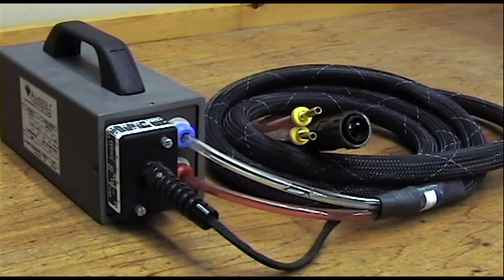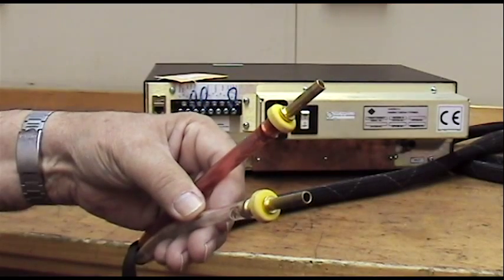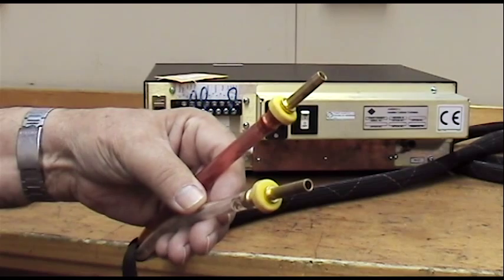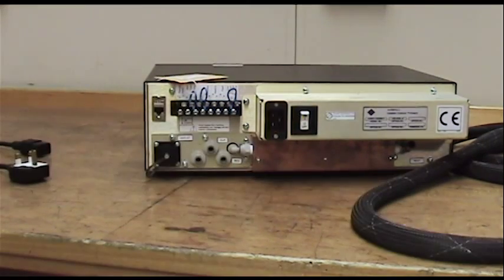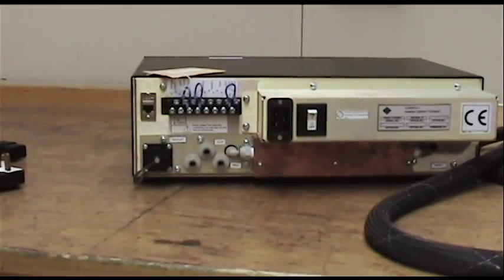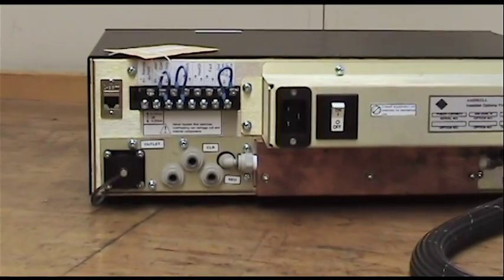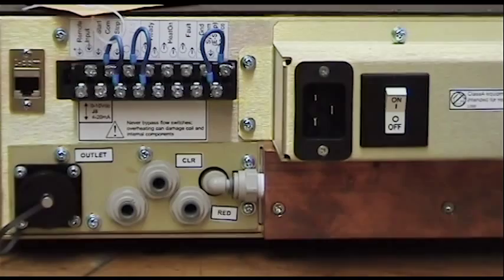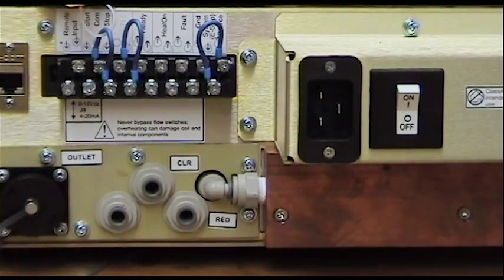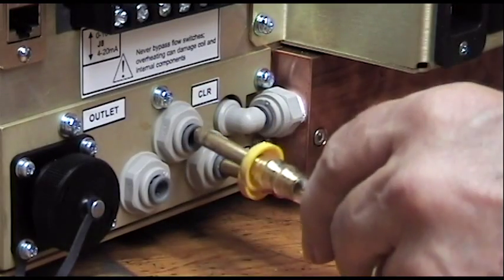Both the cooling water tubes and the electrical feed to the workhead travel in the same sleeve. The water tubes are color-coded. The clear tube carries the cold water first to the workhead and then to the coil. The red tube carries the warm water as it returns. The two tubes connect to the appropriately labeled couplings on the back of the inverter. Simply push them firmly into position. Red and clear.